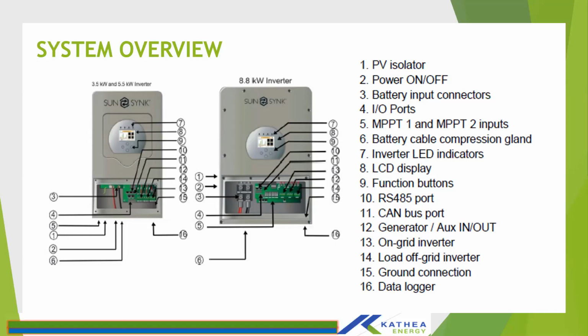Your backup loads should be restricted to the size of the inverter. SunSynk inverters mainly come in, and we distribute, the 5.5 and the 8.8. They have, however, a peak power of 2 times the full load to cater for starting currents in instances of inductive loads, but it can only do that for 10 seconds. So if you have your pumps and all that, it can actually hold power up to 2 times.